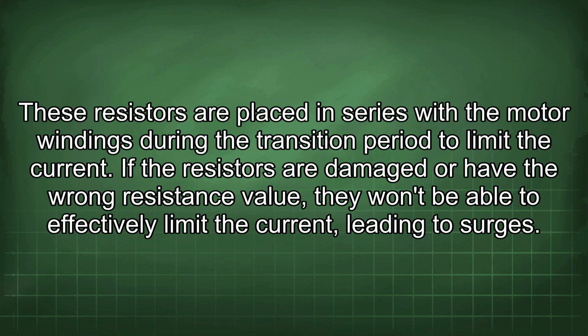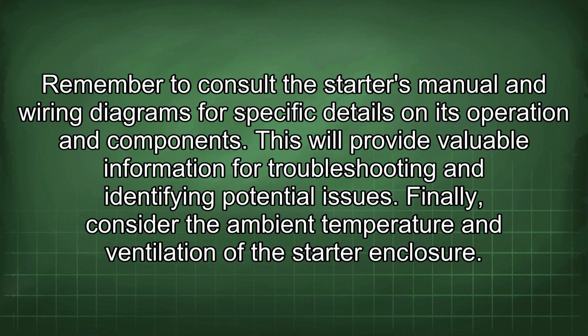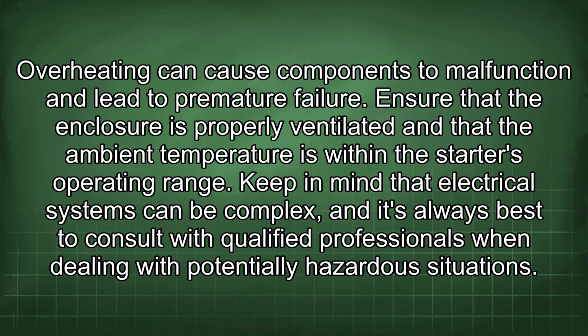Remember to consult the starter's manual and wiring diagrams for specific details on its operation and components. This will provide valuable information for troubleshooting and identifying potential issues. Finally, consider the ambient temperature and ventilation of the starter enclosure. Overheating can cause components to malfunction and lead to premature failure. Ensure that the enclosure is properly ventilated and that the ambient temperature is within the starter's operating range.